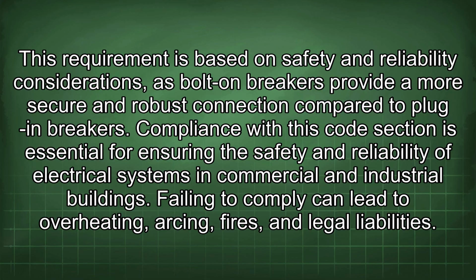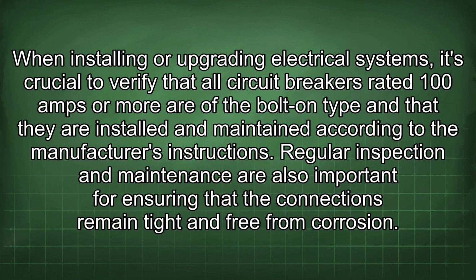Compliance with this code section is essential for ensuring the safety and reliability of electrical systems in commercial and industrial buildings. Failing to comply can lead to overheating, arcing, fires, and legal liabilities. When installing or upgrading electrical systems, it's crucial to verify that all circuit breakers rated 100 amps or more are of the bolt-on type and that they are installed and maintained according to the manufacturer's instructions.